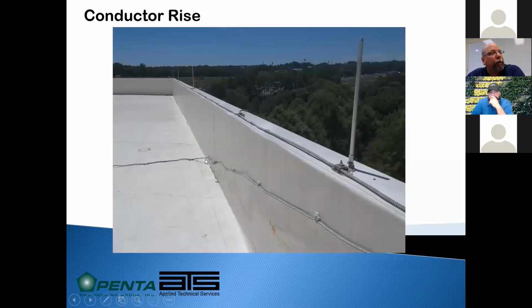Here's an example of a proper rise. So this portion of the cable is coming from the penthouse, comes across the roof. And in this situation, the down conductors are on the outside of the building. So all of the conductor from the penthouse lightning protection has to come over, and any energy from a strike has to climb this wall to get to the parapet loop and then down to the down conductor. So this was installed at a 1/4 slope. I believe this was about a 4-foot parapet wall. So that rise had to run horizontally for 16 feet to make that height.